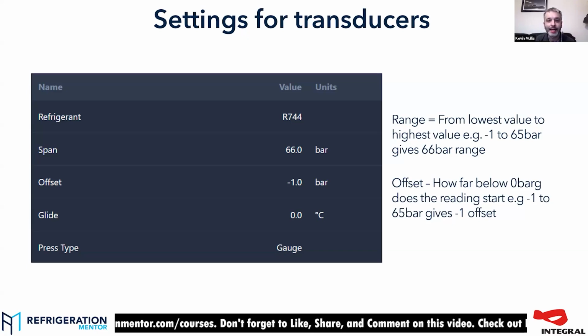The transducer will read that, but the amount of current change on a 4 to 20 milliamp transducer to move it like 0.1, 0.2, 0.3 of a bar is so small, you're inviting errors into it. It's totally just not going to be accurate for you at that range. You can't expect it to be. It's trying to cover 66 bar, and you're asking it to be accurate at the very bottom of its range by 0.1 or 0.2, and that's important when you're doing those gases.